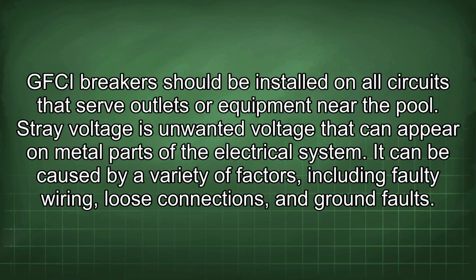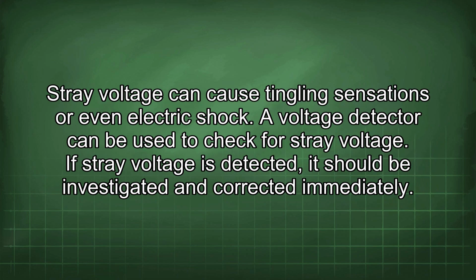Stray voltage is unwanted voltage that can appear on metal parts of the electrical system. It can be caused by a variety of factors, including faulty wiring, loose connections, and ground faults. Stray voltage can cause tingling sensations or even electric shock. A voltage detector can be used to check for stray voltage. If stray voltage is detected, it should be investigated and corrected immediately.